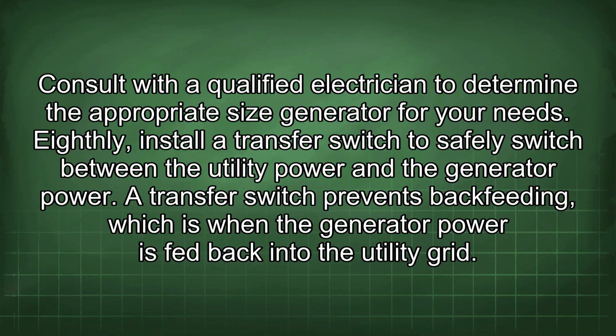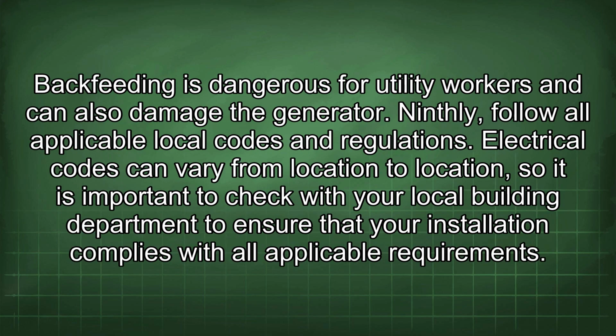Eighthly, install a transfer switch to safely switch between the utility power and the generator power. A transfer switch prevents backfeeding, which is when the generator power is fed back into the utility grid. Backfeeding is dangerous for utility workers and can also damage the generator.